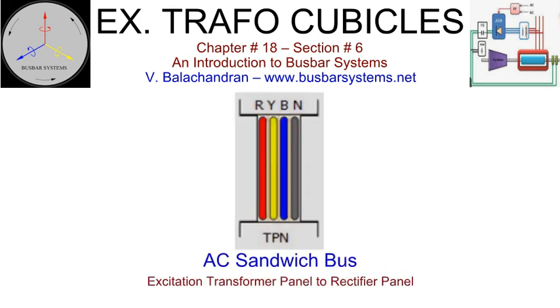The output of the excitation transformer is connected to the input of a 3-phase rectifier cubicle. In the past, the AC power connection from the excitation transformer secondary to the rectifier unit was carried out with copper cables. Each phase had several cables running in parallel. Now the AC connections are being carried out with busways with copper conductor. These are very compact connections and suitable for routing near the generator foundations. These connections are extremely sacrosanct and care is required in establishing their reliability. It is advisable to specify a single copper conductor to carry the rated current.